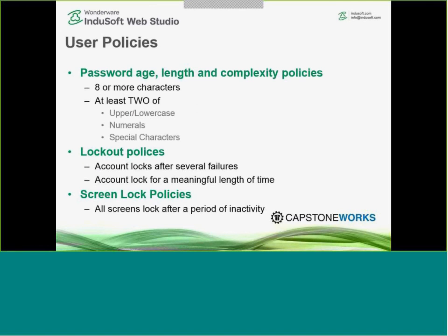User policies can help you enforce this by setting rules, domain-enforced rules or network-enforced rules for password age, length, and complexity, much the way the InduSoft product enforces them there. We generally recommend 8 or more characters and at least 2 of either upper and lowercase letters, numerals, or special characters. We also strongly recommend account lockout policies to lock the account after several failures and lock it for a meaningful length of time or forever, requiring engineer intervention to unlock the account.